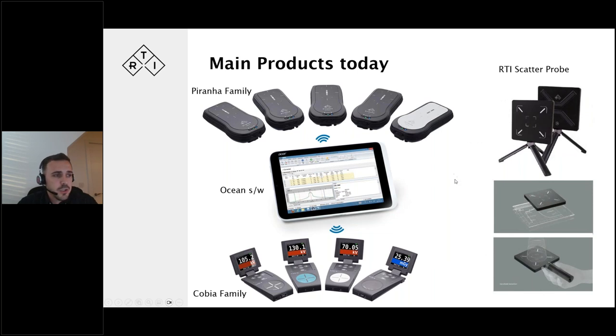The latest addition to our portfolio in recent years was the RTI scatter probe, which detects x-ray scatter and leakage from the x-ray tube and around the x-ray room. This is compliant with regulations such as IEC and CFR, followed by the FDA, so it's fully accredited for those regulations.